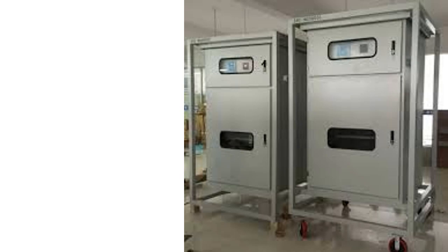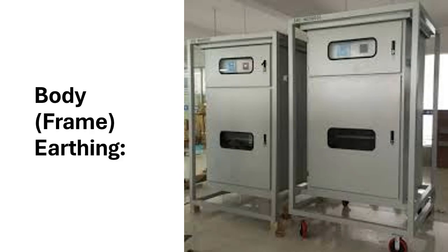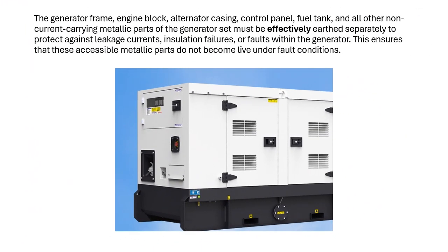Body, frame, earthing. The generator frame, engine block, alternator casing, control panel, fuel tank, and all other non-current carrying metallic parts of the generator set must be effectively earthed separately to protect against leakage currents, insulation failures, or faults within the generator. This ensures that these accessible metallic parts do not become live under fault conditions.